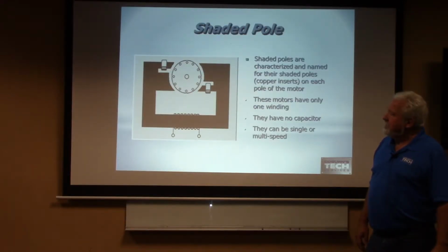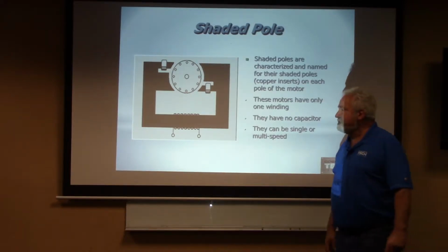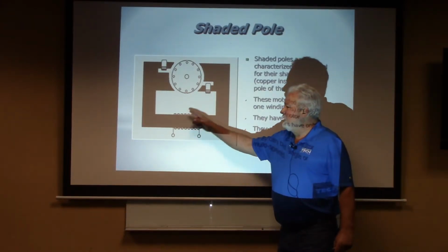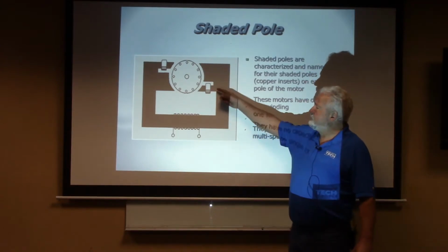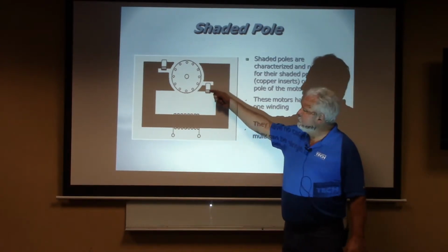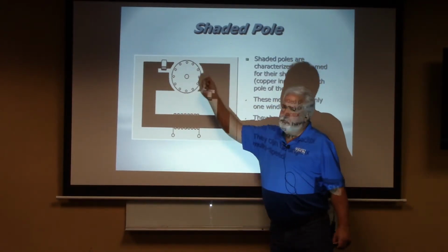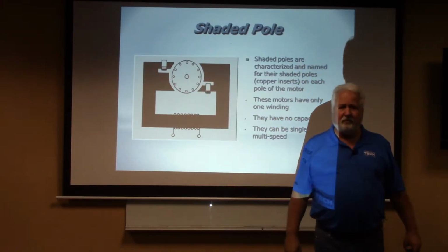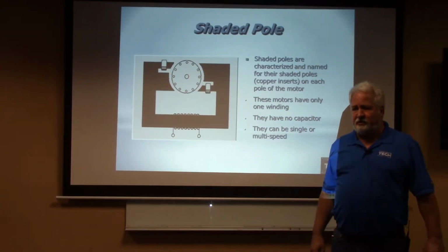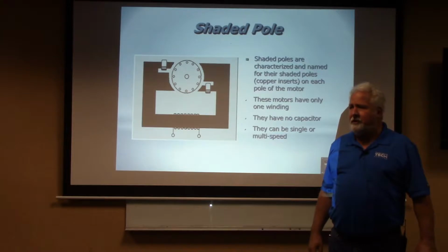So, this is a shaded pole motor. It's got 2 wires that come into it, one in, one back out again. But you'll see on that motor that it's going to have these little pieces of copper on the pole of that motor. That's going to give it direction. It's a shaded pole motor. It does not have a lot of starting torque to it.